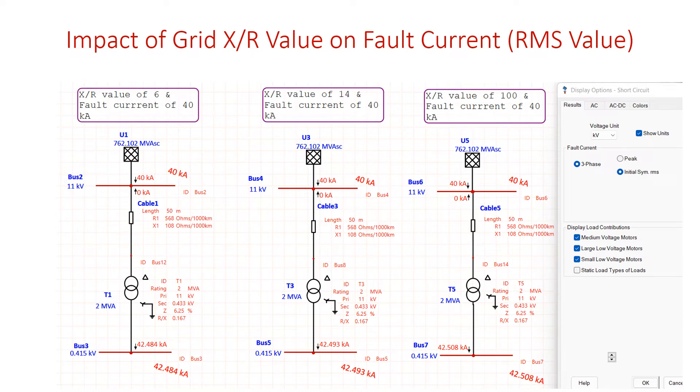Fault is created on bus number 2 as well as bus number 3 where you can see the fault current on bus number 2 is 40 kilo amps and bus number 3 is 42.484. In fact, both these values are initial symmetrical RMS current.